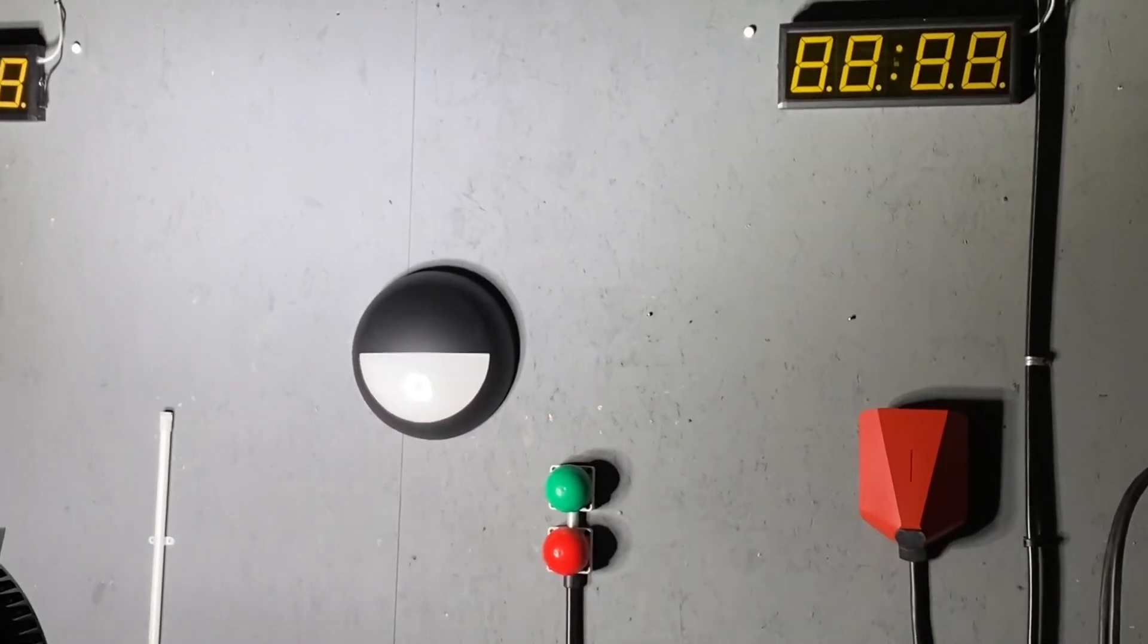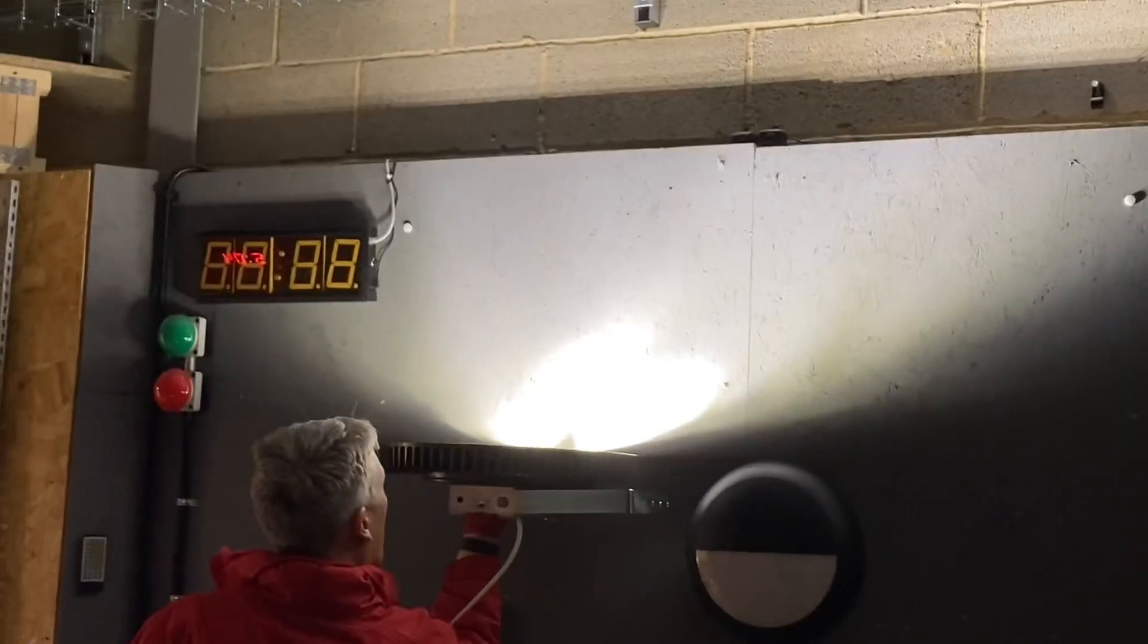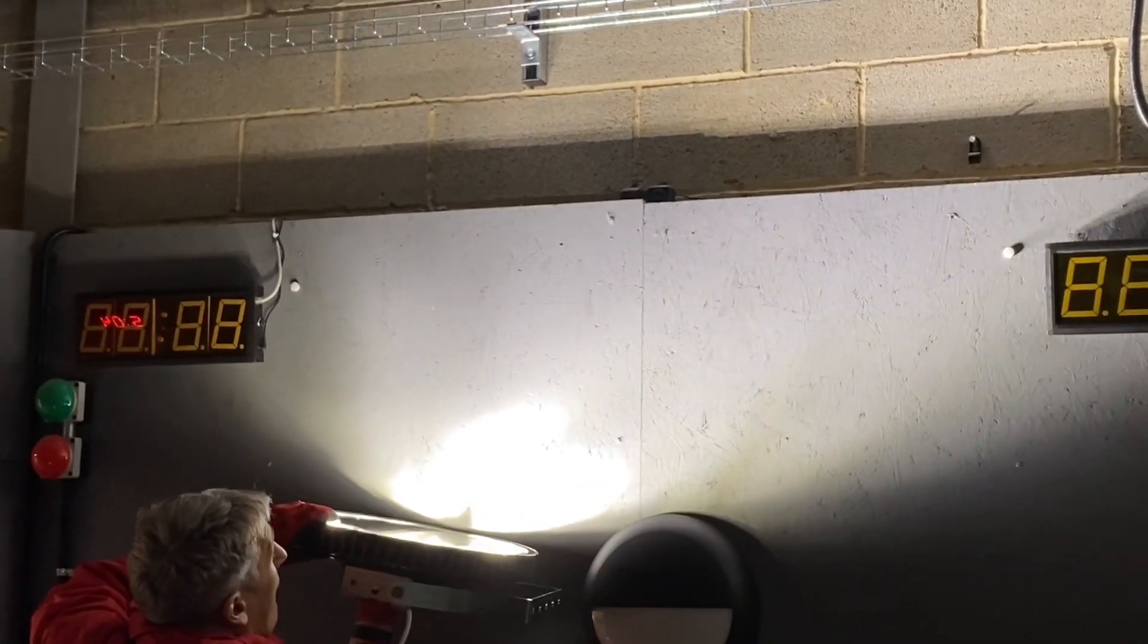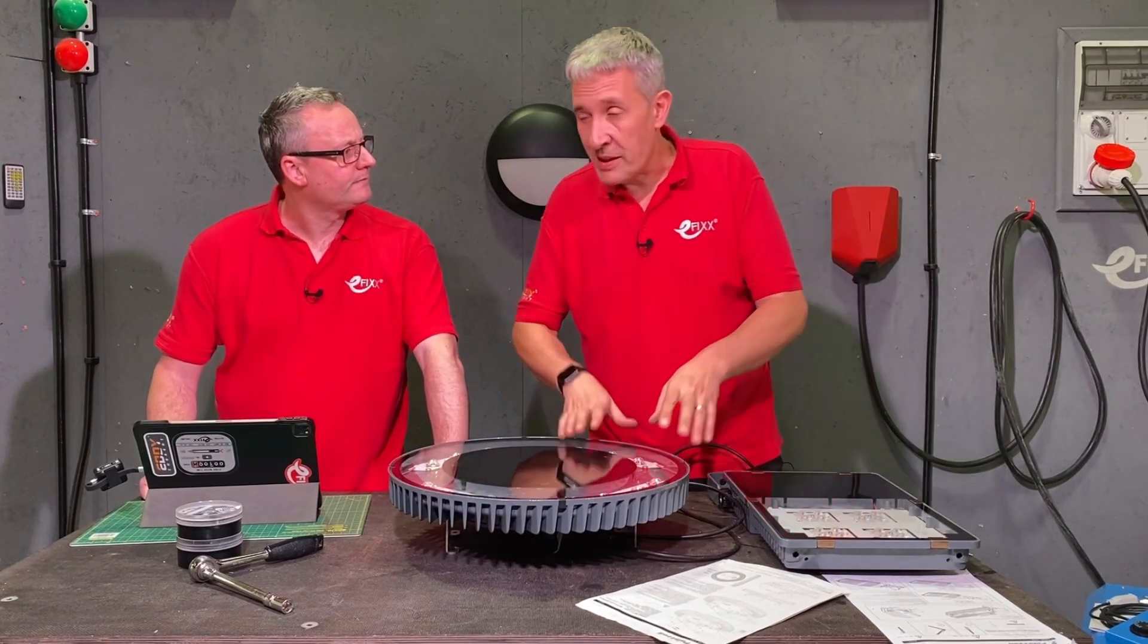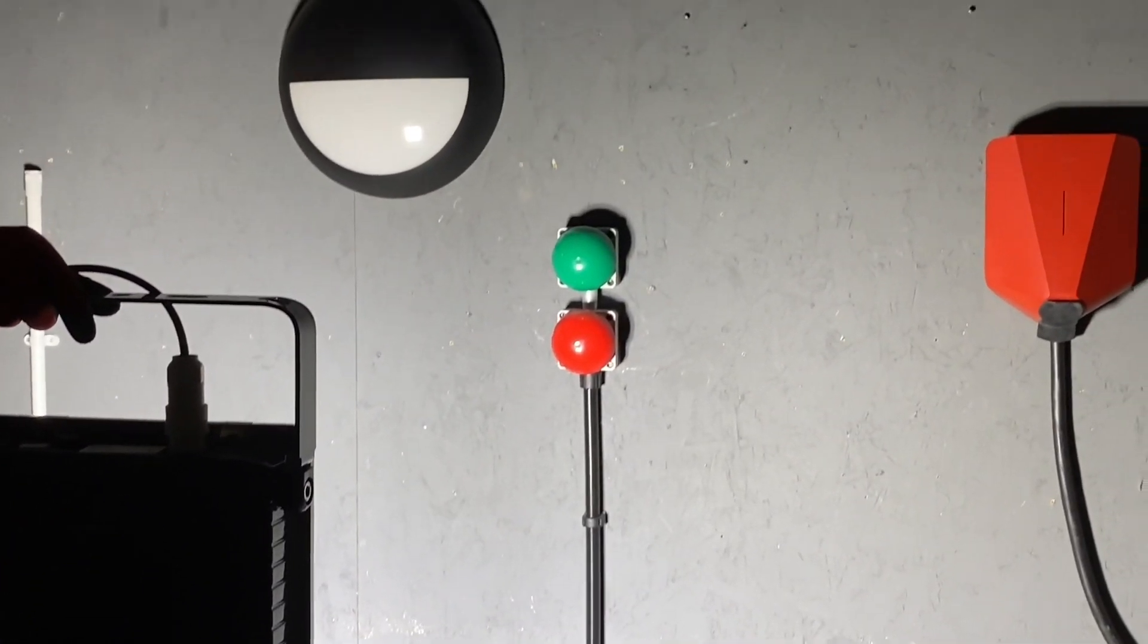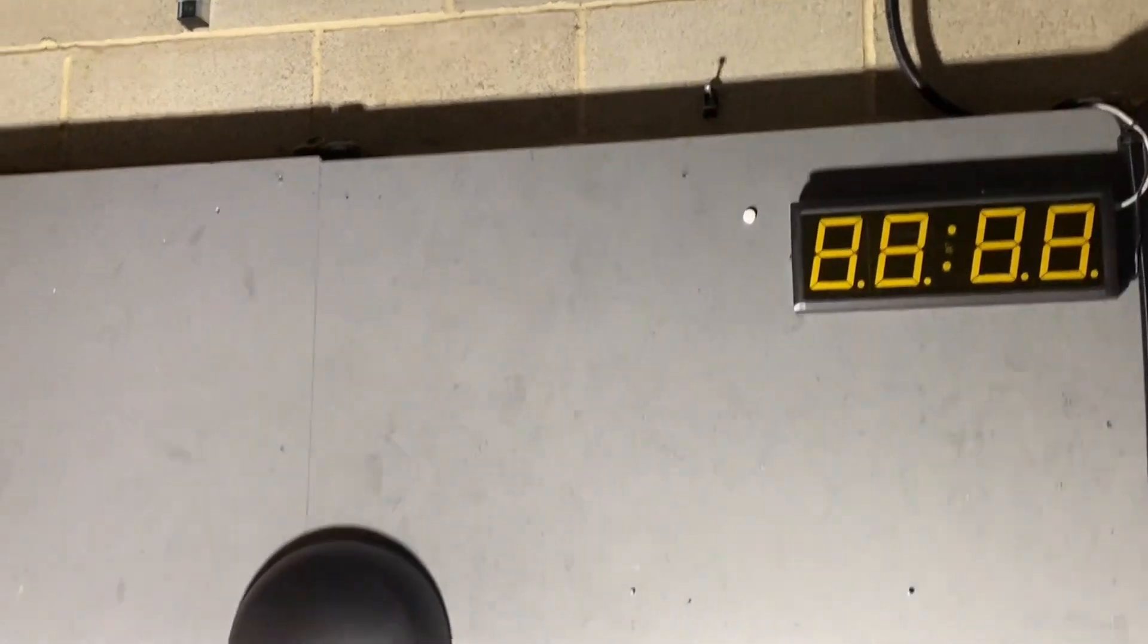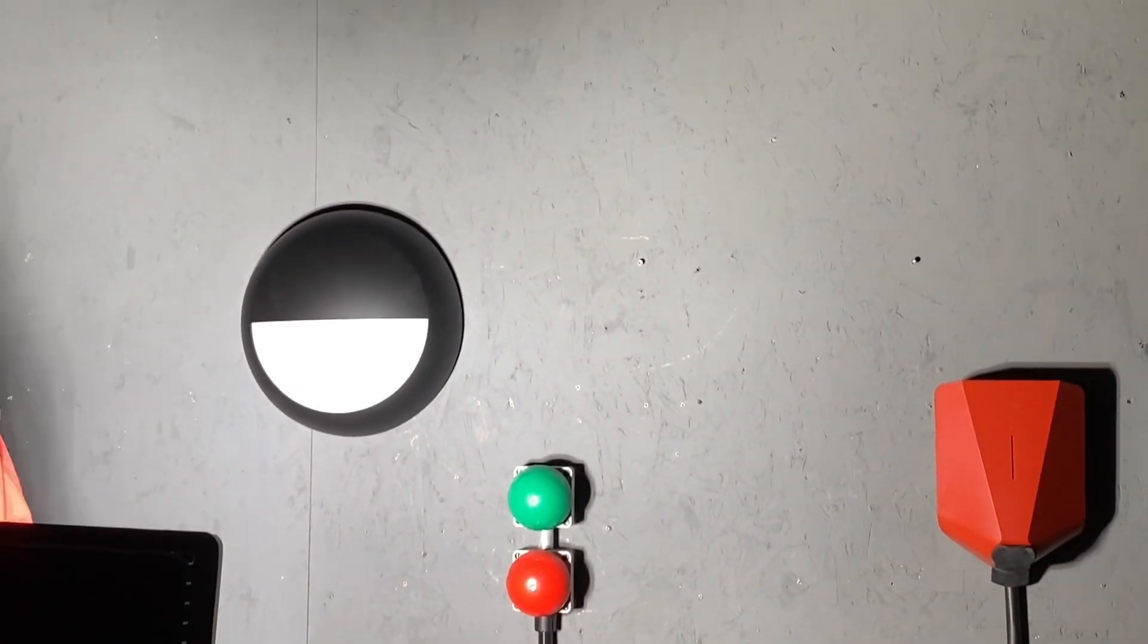However, that comes with that in a factory environment, you've got to think people obviously trying to work. So you've got to minimize things like glare, and so the optics play a part in that. So glare is often something people say, oh, this fitting is low glare. It can be because it's got great optics, but that actually has to be designed in the application, because obviously it depends on where you put that. If you're working on a bench like this, but in the corner of your eye you've got this glare of this really bright light fitting, that obviously causes all sorts of problems. So when we turned them on and we see them there facing the wall, we can see that no light is coming back to where the camera is. The light is being thrown forward, but then because of the optics and how they're obviously designed, we're actually getting light either thrown straight down, and then when we rotate that light fitting round, we can see that that light now is not being thrown down, it's being thrown up, but it's never been thrown back beyond the light fitting.